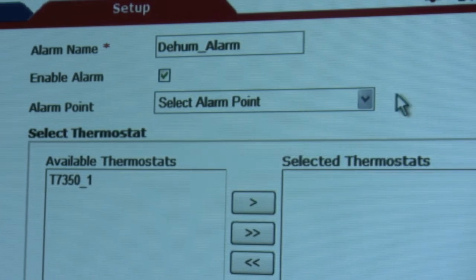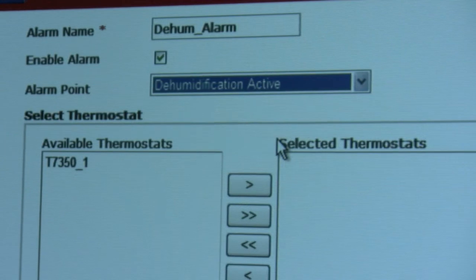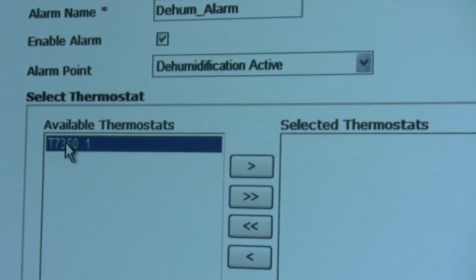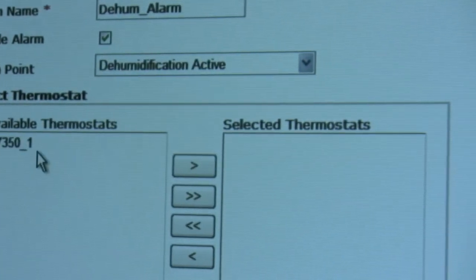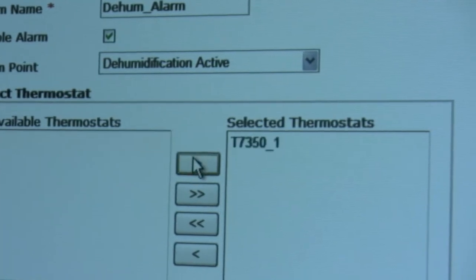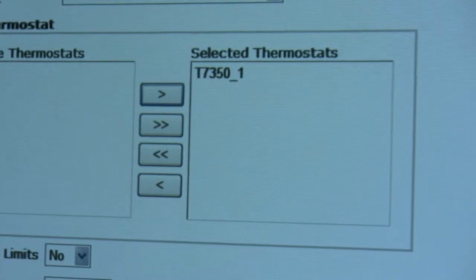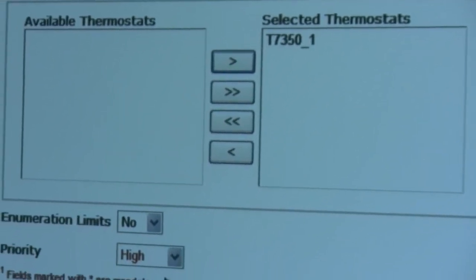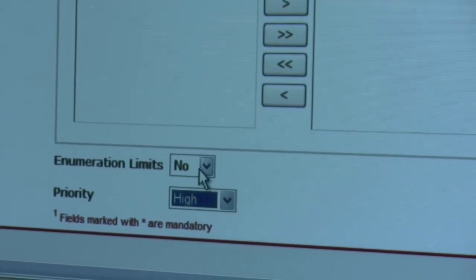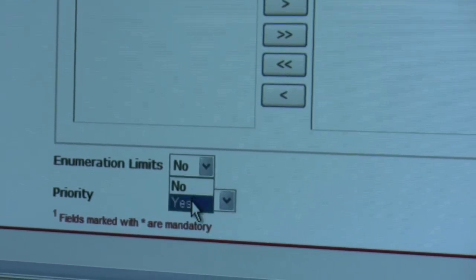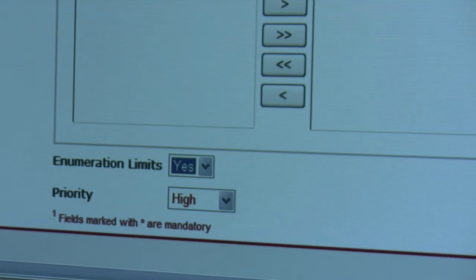We'll name it dehum alarm, we'll select dehumidification active, select the one available thermostat since that's all we have on our system at the time, scroll down, and we can also select the priority. We'll make it a high priority alarm and we'll give it some enumeration limits. Then select save.